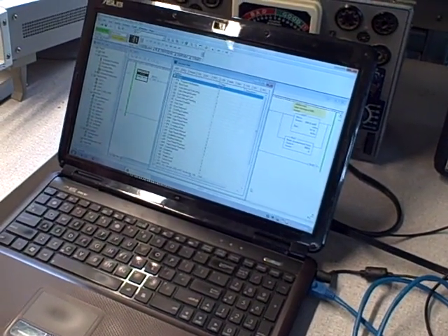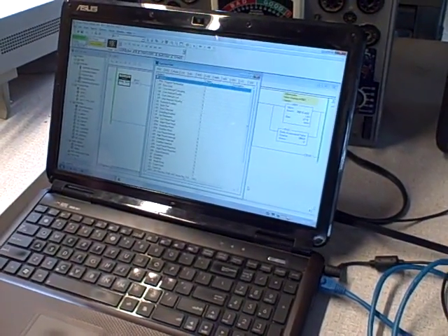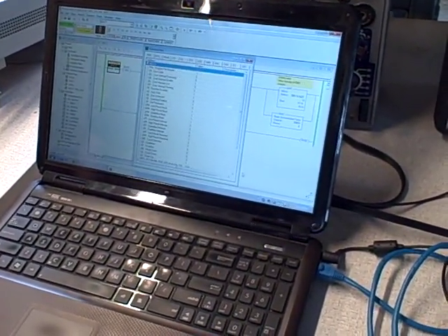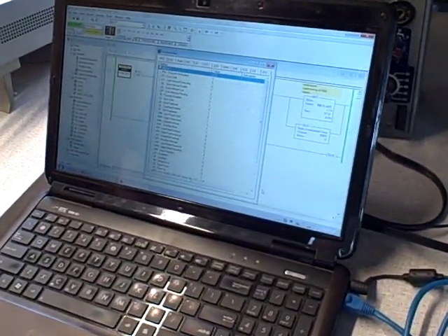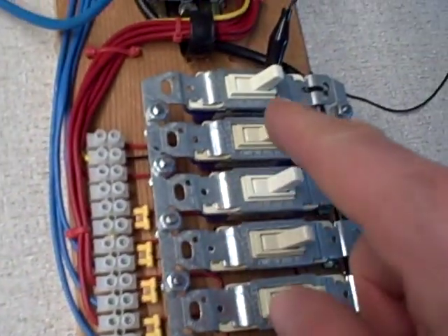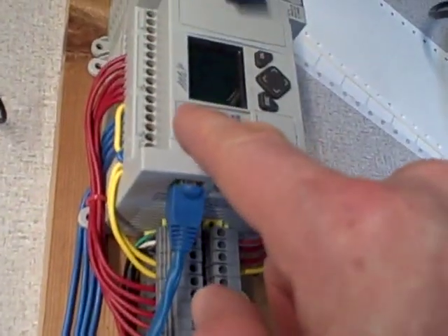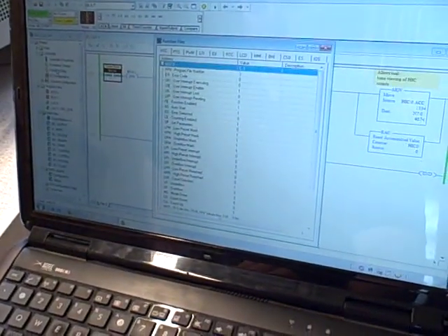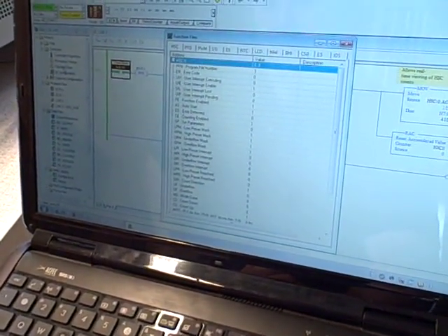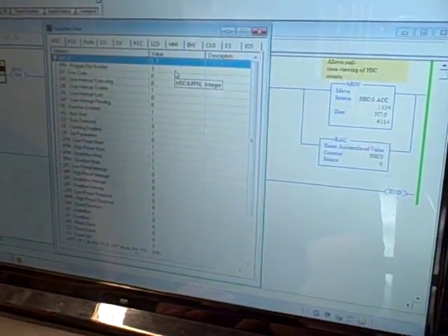The Allen-Bradley MicroLogix 1100 has been configured for high-speed counter operation. The initial configuration steps include wiring to input 0, 1, 2, or 3 on the MicroLogix 1100 for your input. Once you've done that, you'll need to go to your RSLogix 500 function file, choose the HSC tab, and the following parameters at a minimum must be configured.